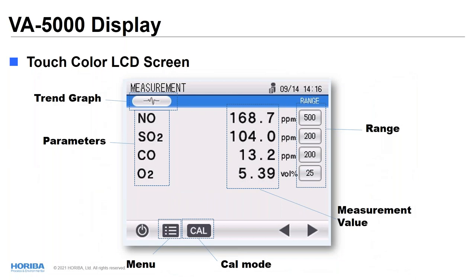All right, this one is the main display, and I'm trying to look in more detail here. As you can see, it shows the four parameters at the same time. It's very readable, and the measurement value is shown here. These are showing some range information. So NO is measuring 168 ppm at the 500 ppm range. And once you tap this 500 button, you can select a different measurement range. It's pretty easy to operate.